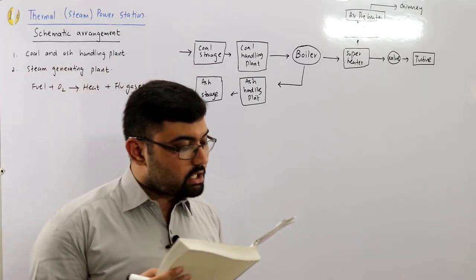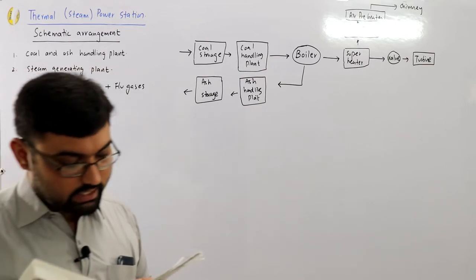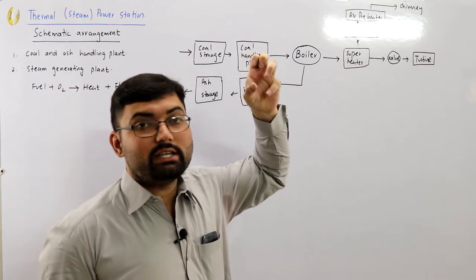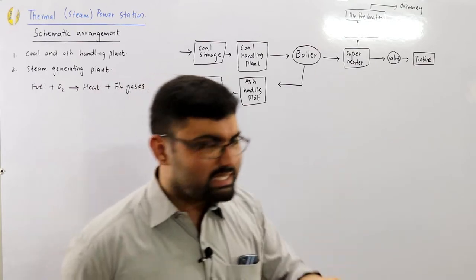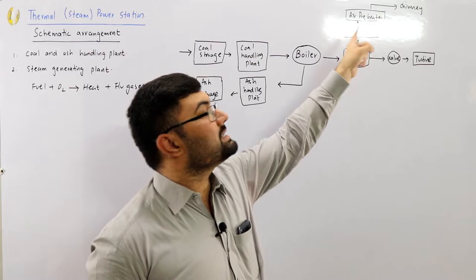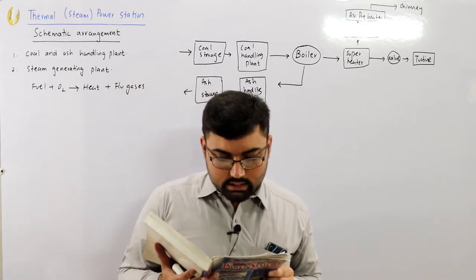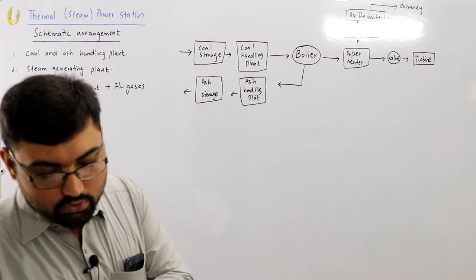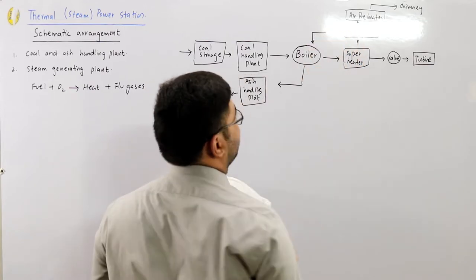An economizer is essentially a feed water heater — it derives heat from the flue gases coming from the superheater. The feed water coming from the condensate is fed into the economizer, where the heat from the flue gases is used to heat the feed water. This heated feed water then goes back to the boiler.